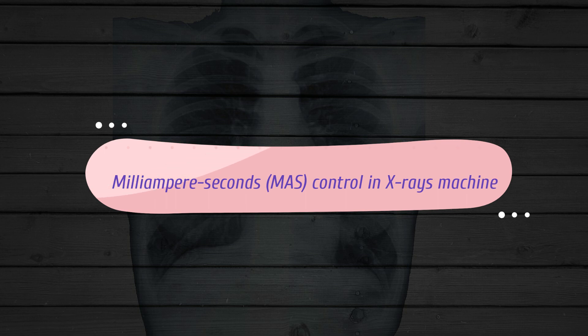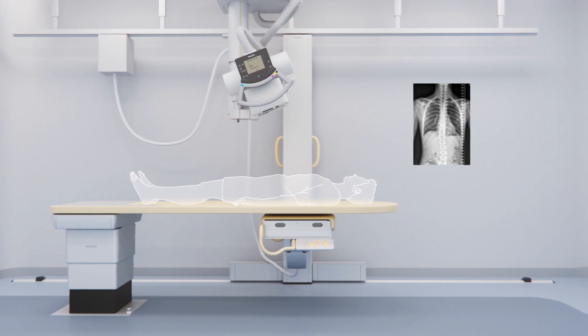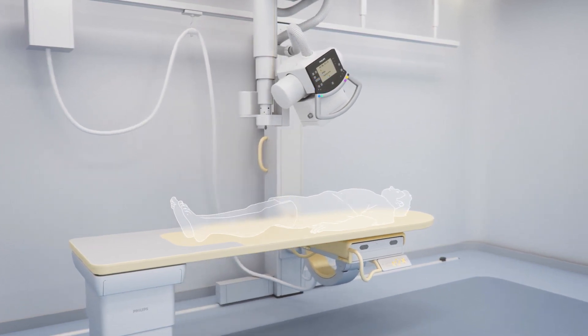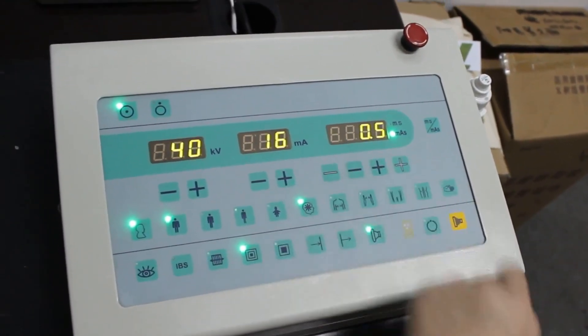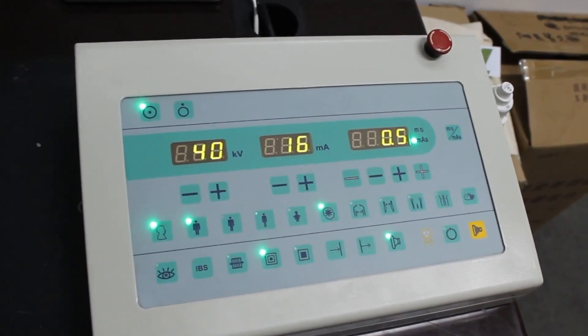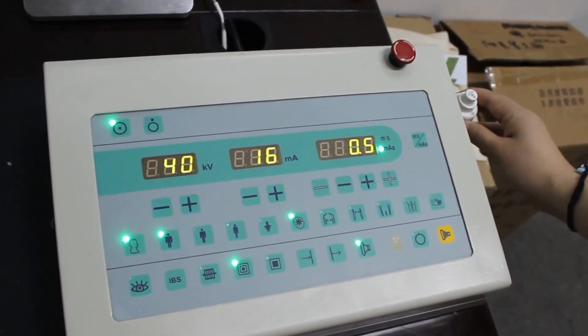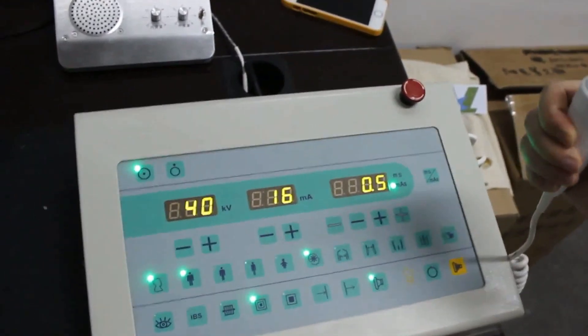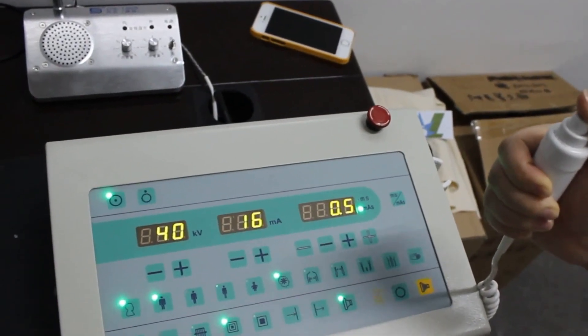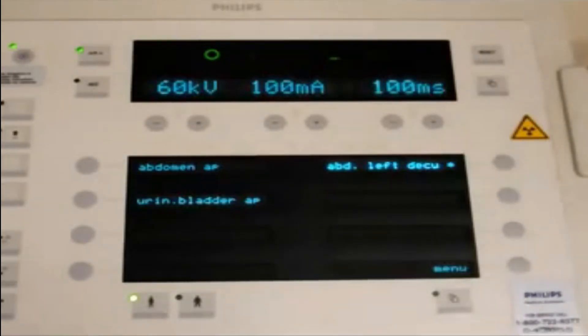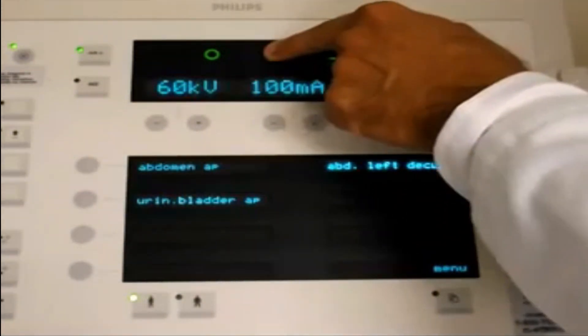Let's look into milliampere seconds, or MAS control in x-ray machines. MAS is a measure of radiation produced — milliampere over a set amount of time in seconds — via an x-ray tube. It directly influences the radiographic density when all other factors are constant. An increase in current (MA) results in a higher production of electrons inside the x-ray tube, which will therefore increase the quantity of radiation. More radiation causes more photons reaching the detector, and hence apparent structural density and signal intensity will increase. The time factor prescribes how long MA will last. The reciprocity law states that a reaction of photographic emulsion to light equals the product of the intensity of that light and the time of exposure. This pertains to MAS in the sense that all combinations of MA and time that amount to an equal quantity will produce the same amount of density.